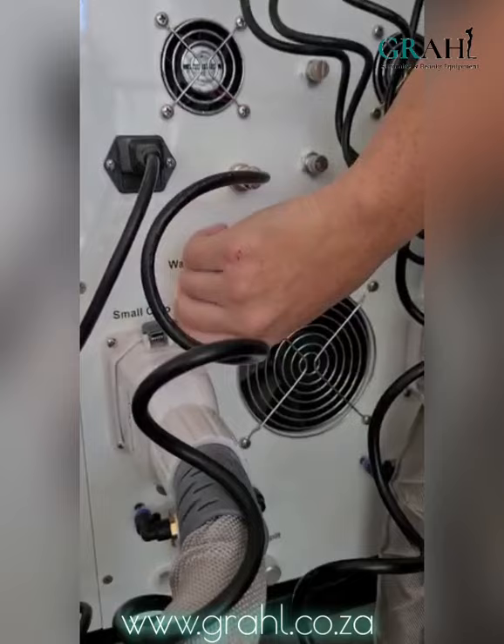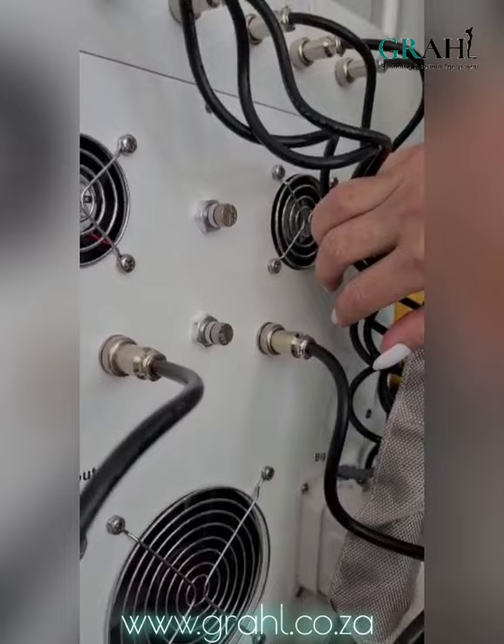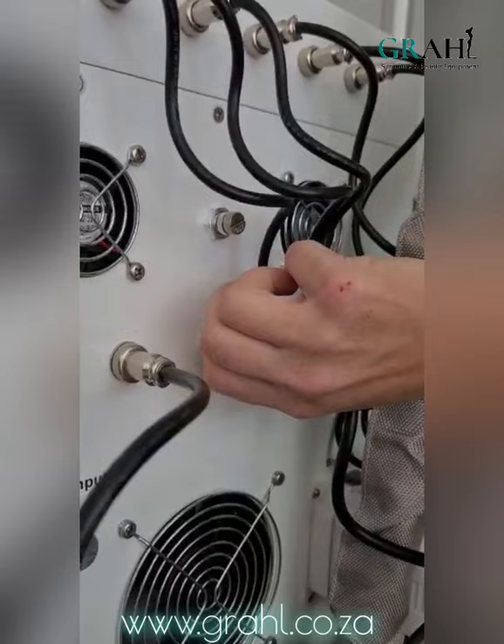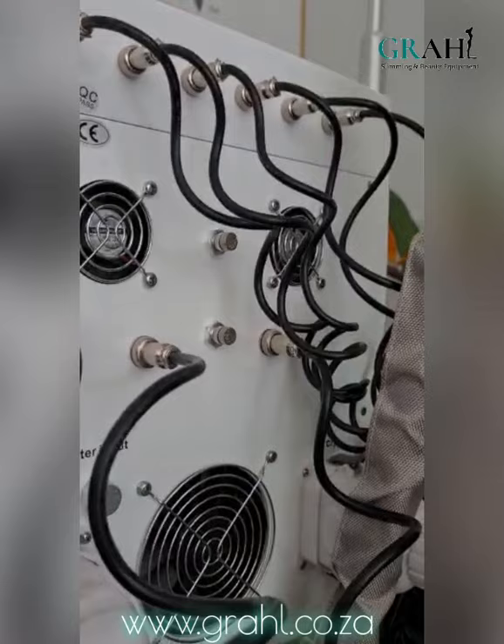The final thing on the back of the machine that I want to talk to you about is these two silver nozzles over here, and these are for the suction on the fat freeze handles. If you turn them to the right you'll feel that it's quite tight, which means that the suction is going to be quite strong. The top one is for the big cryo head and the bottom one is for the small cryo head.